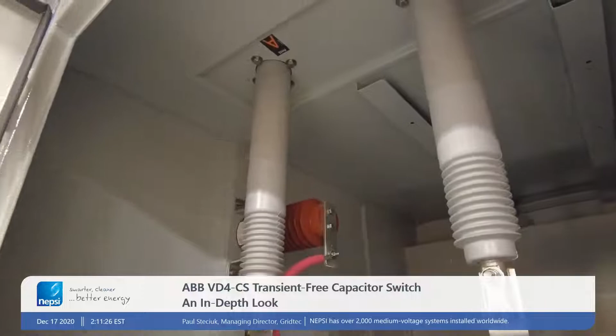Is there any restriction on the capacitor bank connection, grounded versus ungrounded? Oh yes, it has to be Y ungrounded, not delta. And then if you could speak a little about phase rotation...